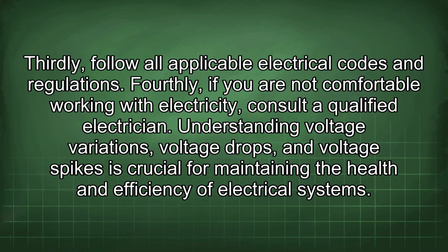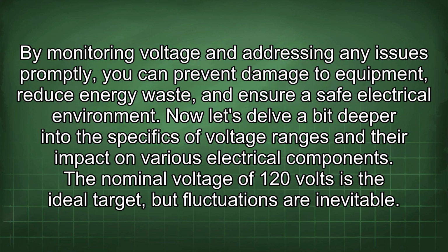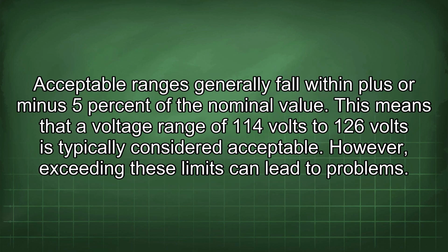Understanding voltage variations, voltage drops, and voltage spikes is crucial for maintaining the health and efficiency of electrical systems. By monitoring voltage and addressing any issues promptly, you can prevent damage to equipment, reduce energy waste, and ensure a safe electrical environment. Now let's delve a bit deeper into the specifics of voltage ranges and their impact on various electrical components. The nominal voltage of 120 volts is the ideal target, but fluctuations are inevitable. Acceptable ranges generally fall within plus or minus 5% of the nominal value. This means that a voltage range of 114 volts to 126 volts is typically considered acceptable.